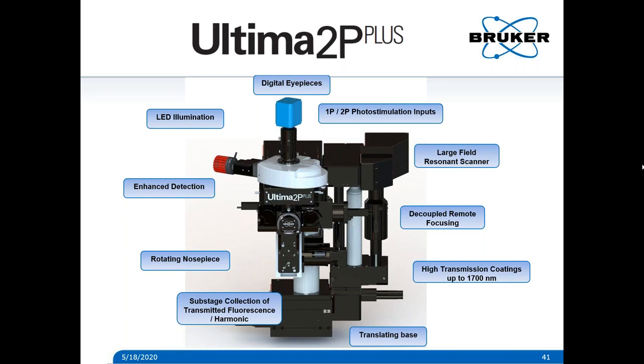Second question: is it possible to use an SLM or a deformable mirror to enhance the resolution of a single focus spot? Yes — this is the technique of adaptive optics, where wavefront distortions along the optical path can be corrected using an SLM lens function to get a better focus spot. A lot of adaptive optics implementations are a little bit slow — you have to correct for aberrations, and if you change your sample or focal plane it interferes with workflow. But it's theoretically possible in any system with an SLM conjugated to the back aperture of the objective, like ours.